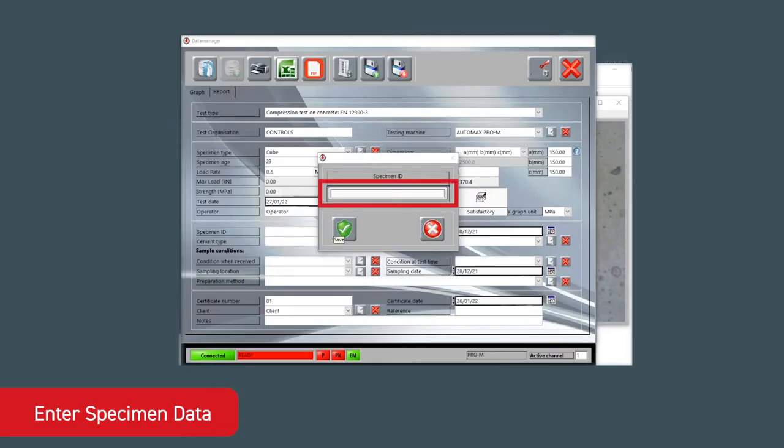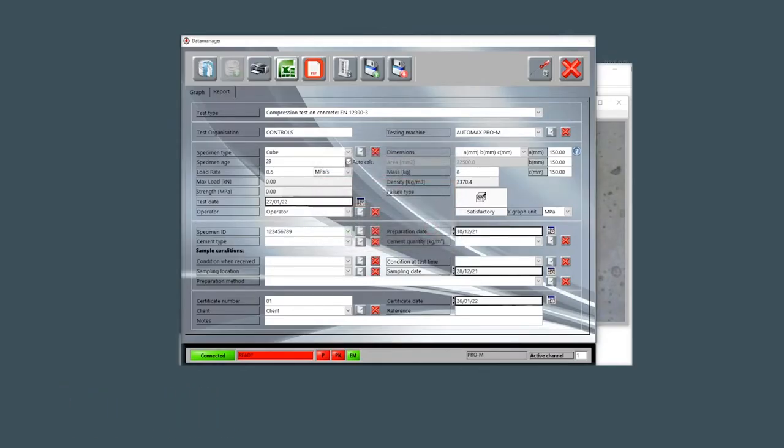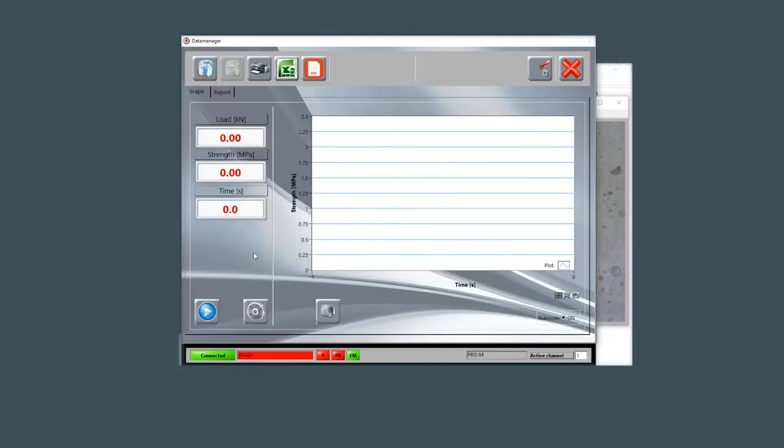Enter the specimen data such as the ID number and then move to the graph window. Here, it's possible to activate the SID reader function and select the correct options in case of a wrong barcode being recognized.